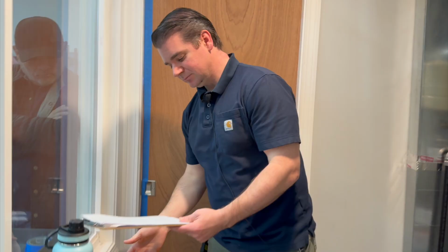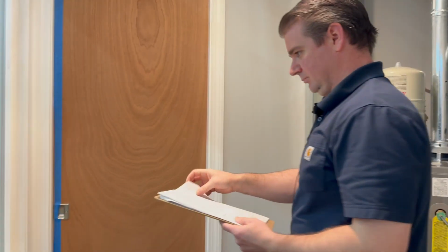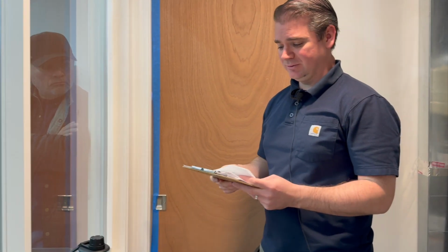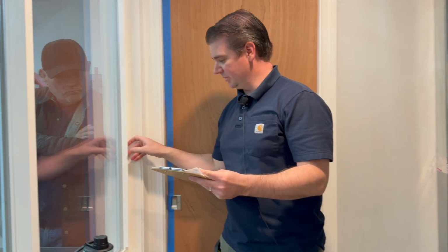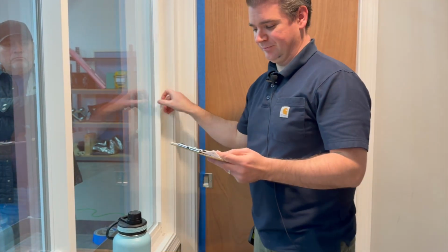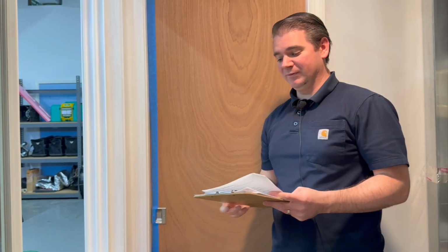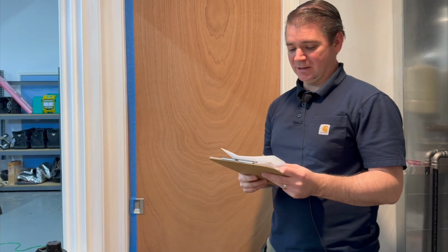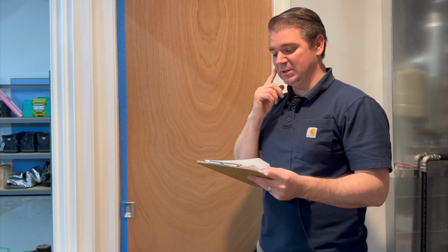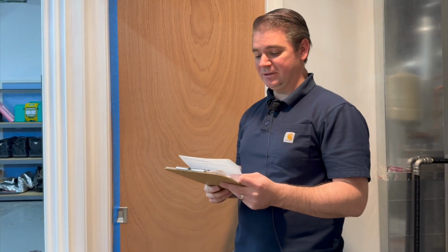Number 7, two conditions that can impact the performance of supply air: if the register is blocked or if the damper is closed. Two conditions that can impact the performance of return air: if the duct is blocked or the filter is dirty. Two conditions that can impact the performance of hydronic baseboard heating: if the aluminum fins are damaged or if they're covered with cat hair. Three potential negative impacts when the distribution system is located outside the thermal envelope: comfort problems, ice dams, and energy loss.